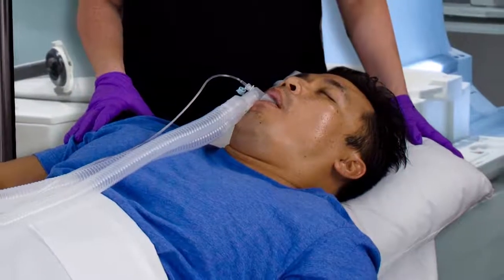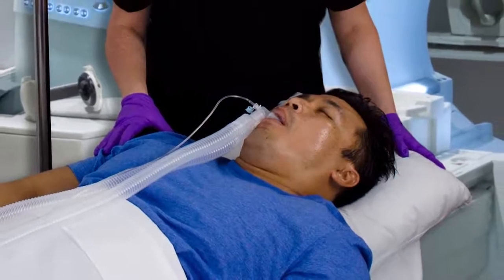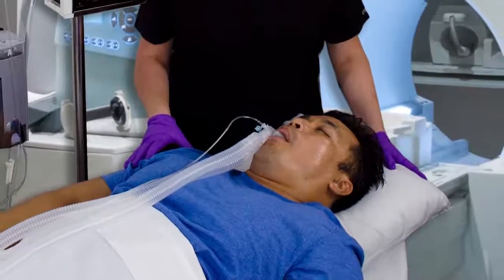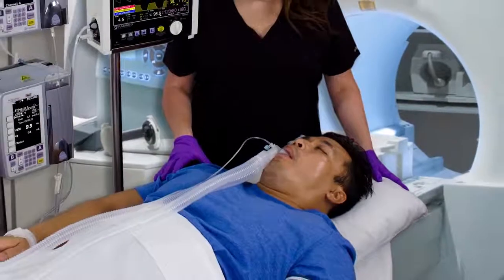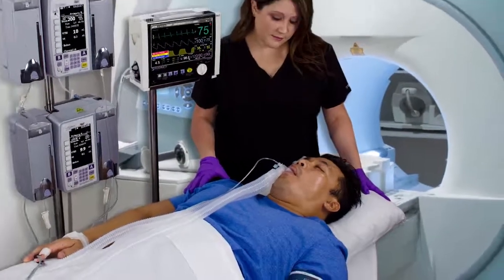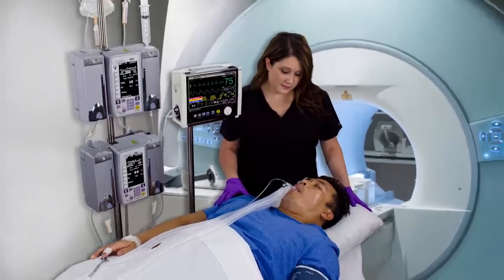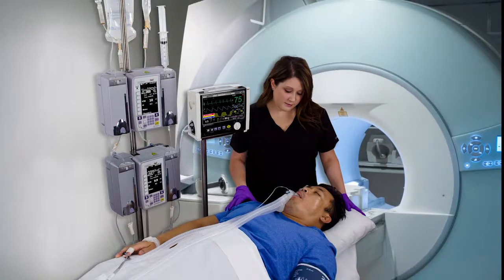Before entering the MRI room, also known as Zone 4, be sure to place the O-Pod on a blanket or towel to minimize MR vibrations. As a best practice, it is recommended the hand being used to monitor SPO2 is covered with a blanket to prevent ambient light from potentially affecting the patient's readings.